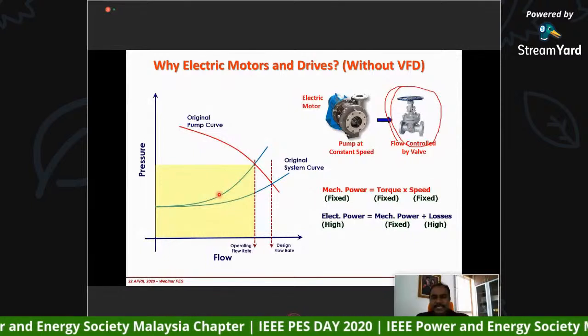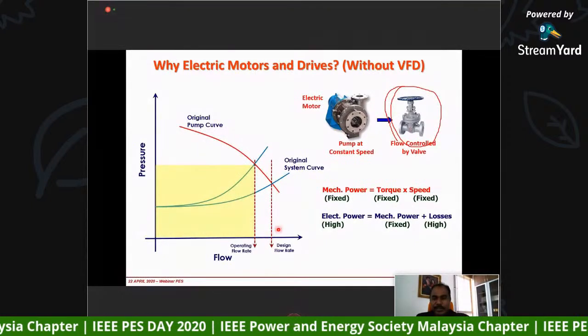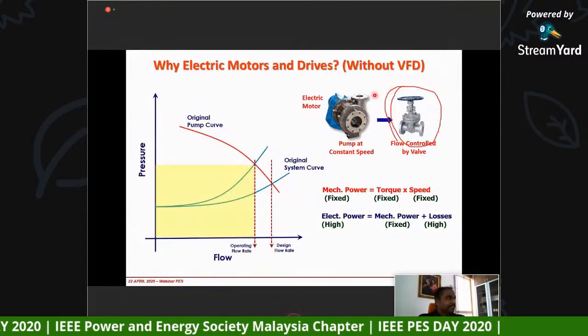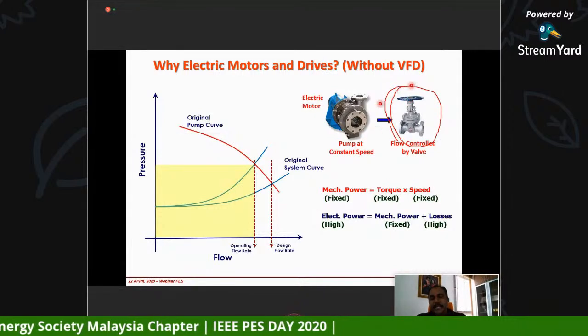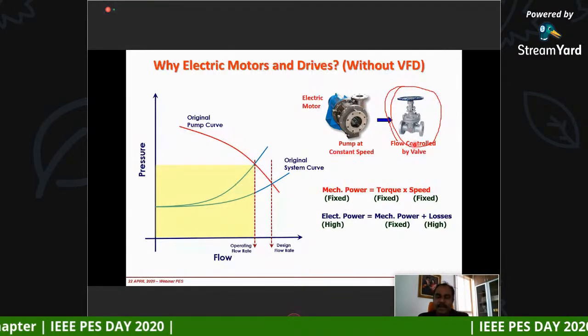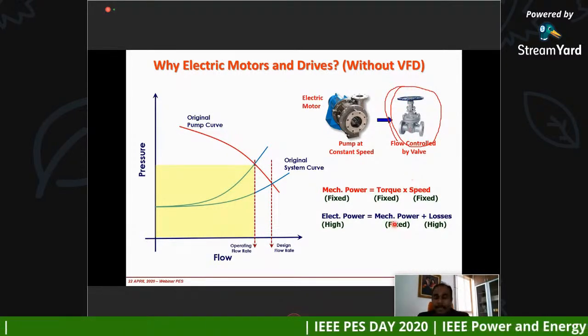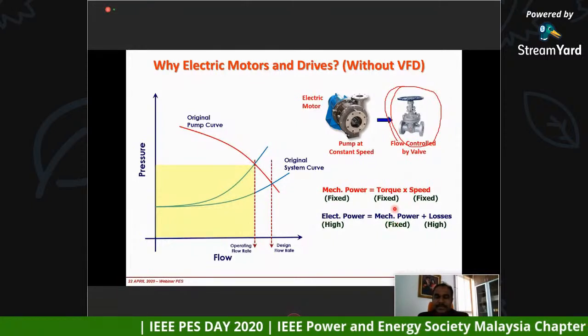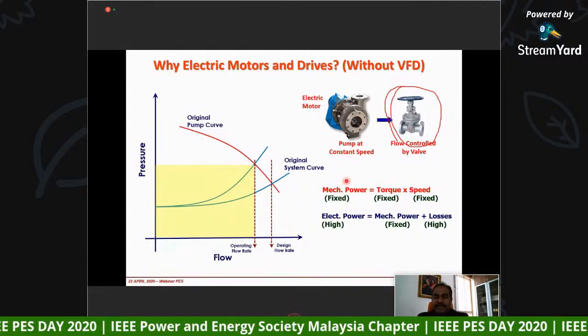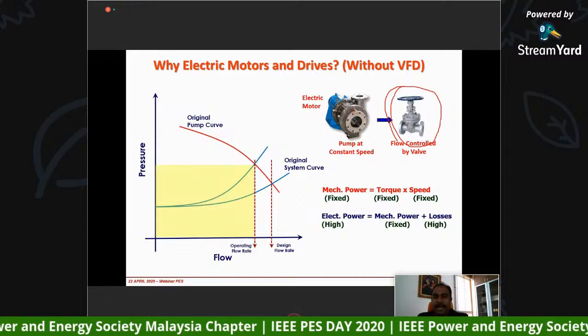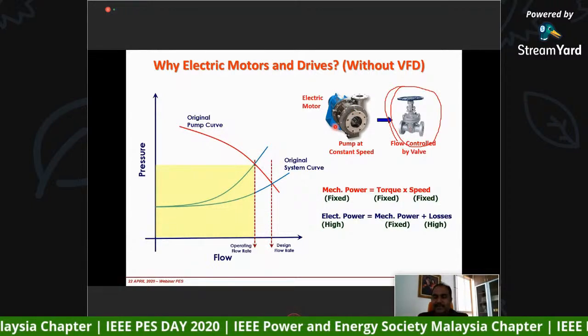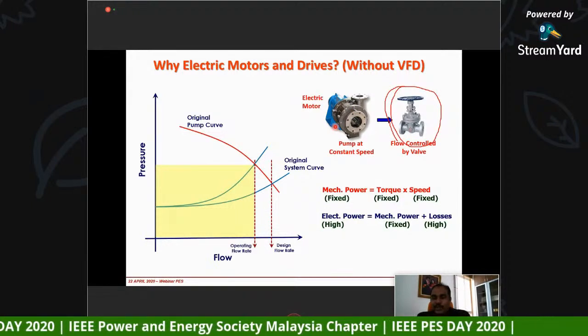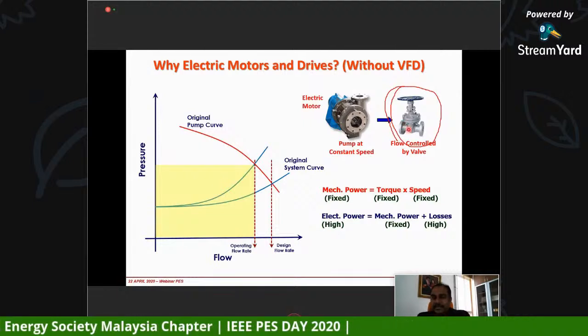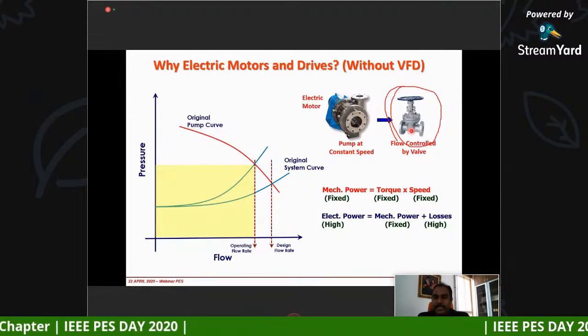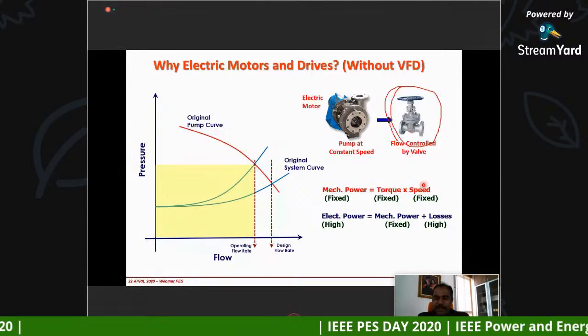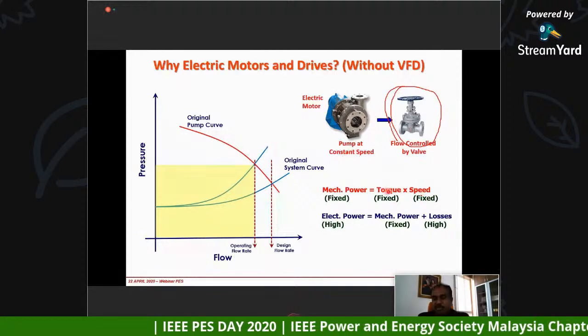Okay. In this case, even though you reduce the flow by reducing the mechanical valve, you will notice that the mechanical power is going to be about the same, because the pump, the motor is still running at full speed. You don't actually do anything on the speed, but the flow rate is controlled by using a mechanical valve, and therefore there's not much change in the speed. Torque more or less is going to be there.